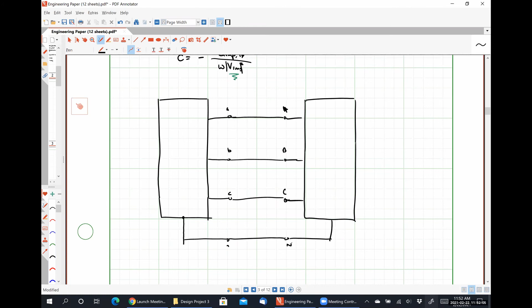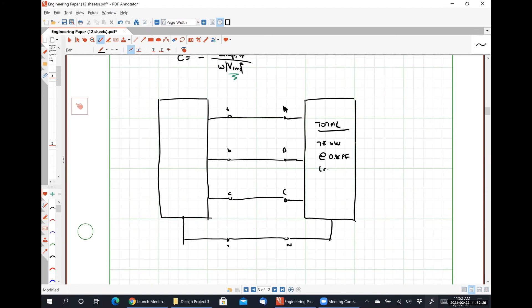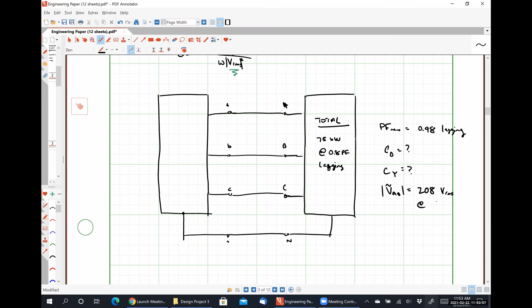Let's say our load is absorbing in total, meaning over all three phases, 75 kW at 0.8 power factor lagging, and we want our new power factor to be 0.98 lagging. What value of capacitor would we use in a delta configuration, and what value would we use in a Y configuration? We are told that the magnitude of voltage VAB is 208 volts RMS at a frequency of 60 hertz.